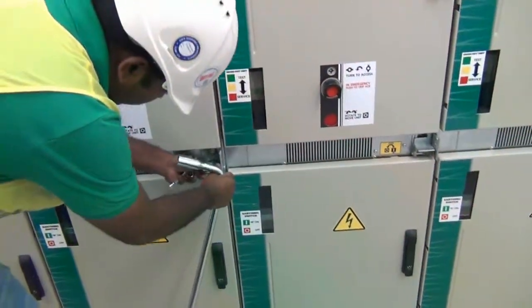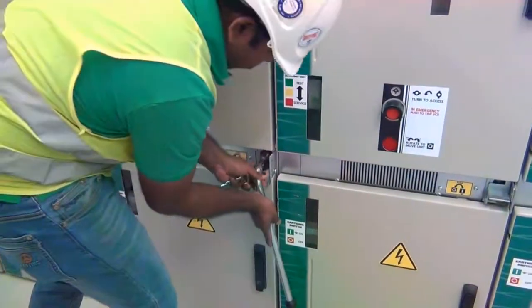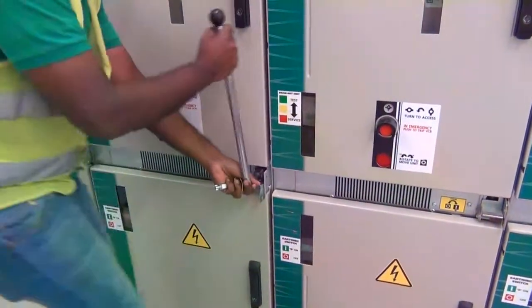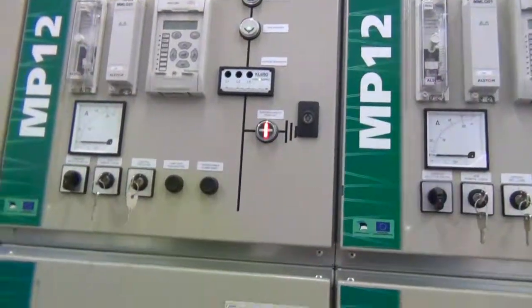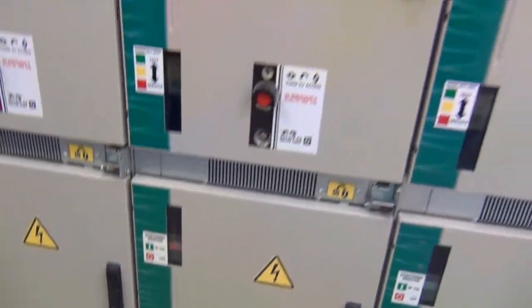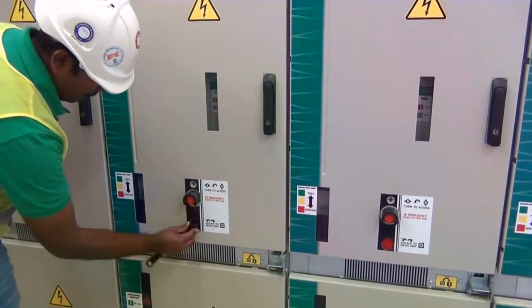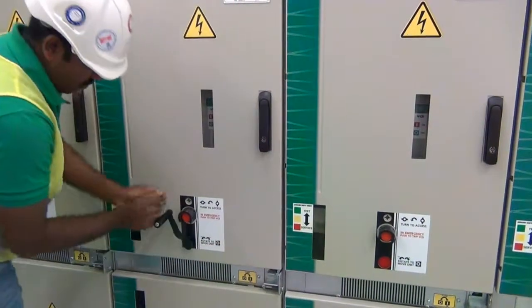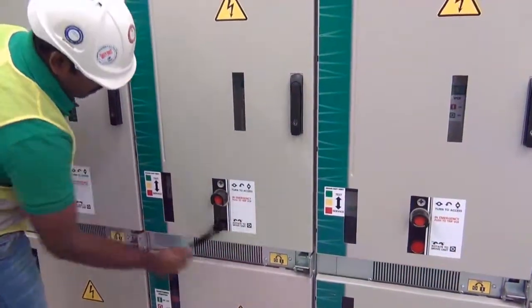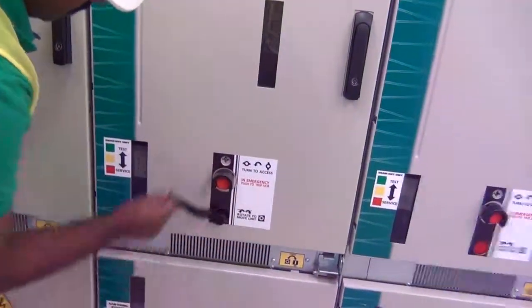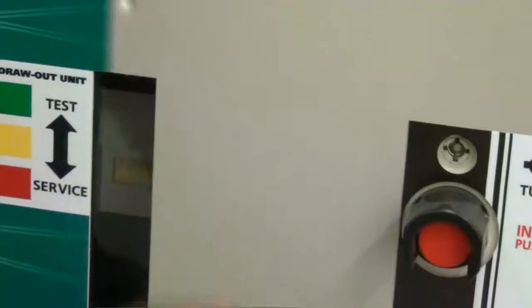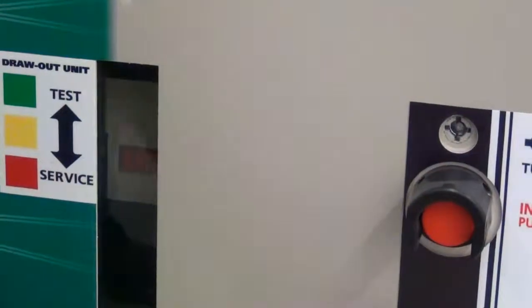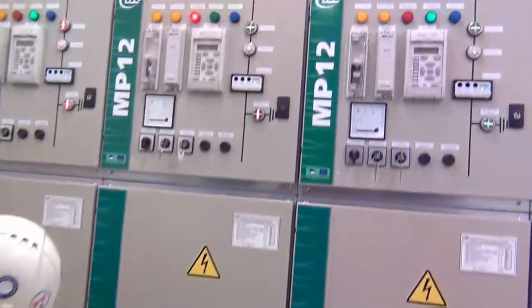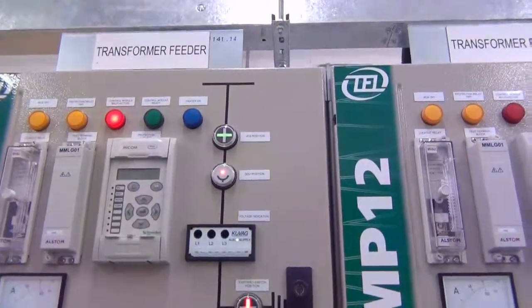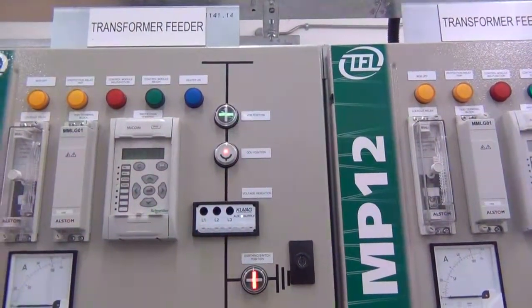So the earth switch is now disconnected from earth, and now the earth switch is disconnected, as you can see here as well, and now you will be able to rack in the breaker. So this is the first interlock that should be present, and as you can now see, the breaker is changing its condition. It's going in, it is in an intermediate condition, and as soon as it turns red, it's in service condition. Now the earth switch is off, the VCB is in off condition, but the drawout unit clearly shows that it is in service.